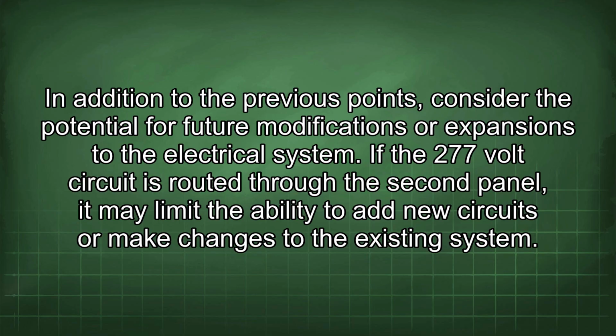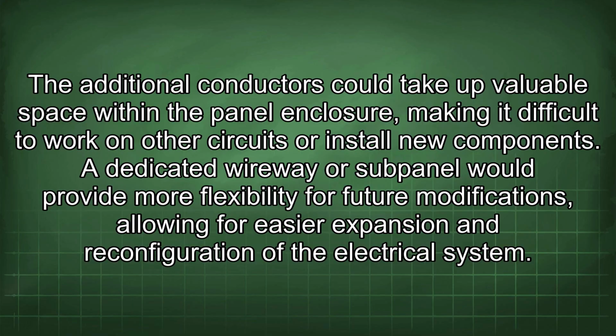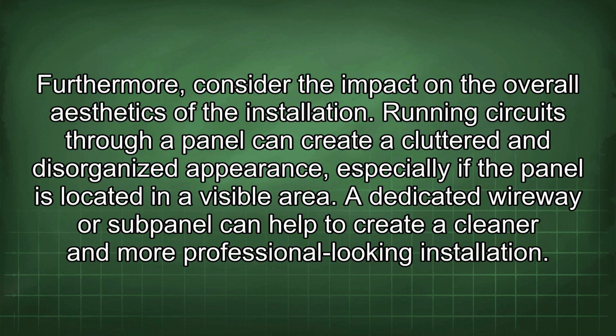In addition to the previous points, consider the potential for future modifications or expansions to the electrical system. If the 277-volt circuit is routed through the second panel, it may limit the ability to add new circuits or make changes to the existing system. The additional conductors could take up valuable space within the panel enclosure, making it difficult to work on other circuits or install new components. A dedicated wireway or subpanel would provide more flexibility for future modifications, allowing for easier expansion and reconfiguration of the electrical system. Furthermore, consider the impact on the overall aesthetics of the installation.